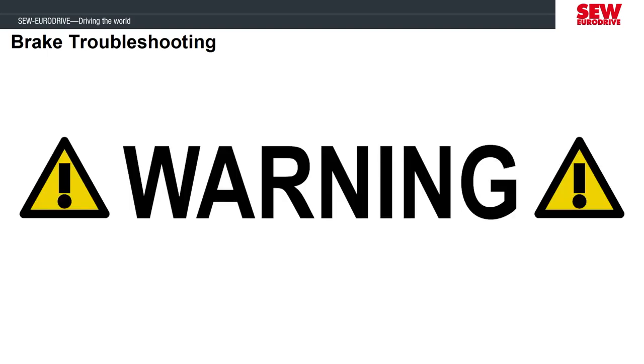Before troubleshooting the brake, be aware it can be very dangerous. There is high voltage present, and if the brake is accidentally released while troubleshooting, the machinery or voltages could kill you. The brake also gets hot enough to burn you. You need to be qualified in working with high voltages and must use personal protective equipment with lockout/tagout procedures. You also need to lock the mechanics of the machine from falling or moving — for example, brakes on our motors could be holding a load suspended in the air or holding back spring tension in the application. If the brake is released without motor power, the load would fall or spring tension could release, which could be catastrophic.